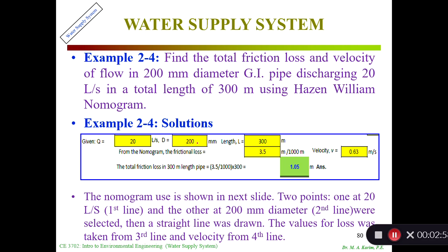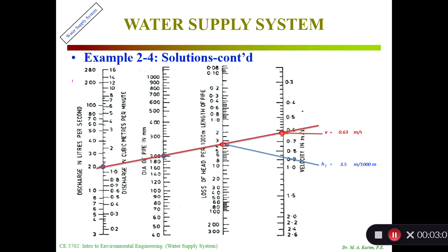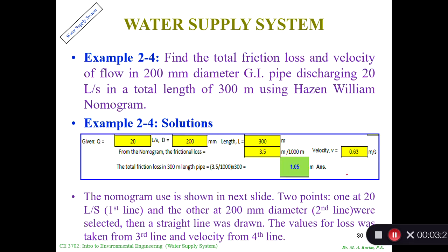Here are the given values: 20 liters per second and 200 millimeters diameter. From the nomogram, if I put here 20 liters per second and 200 millimeters diameter, I get two points. If I add the two points and extend the line as a straight line, I get HF loss of 3.5 meters per 1000 meters and velocity of 0.63 meters per second. That's what I got. I put those values here, from the graph.